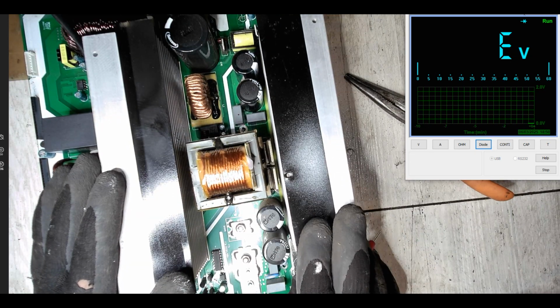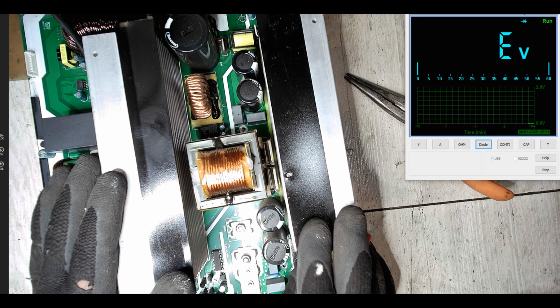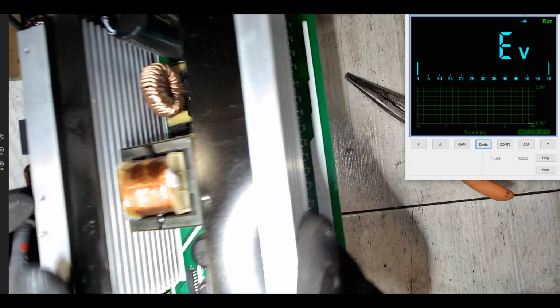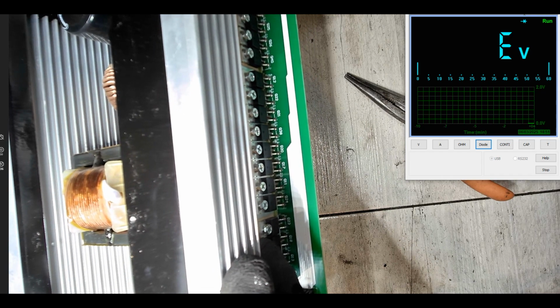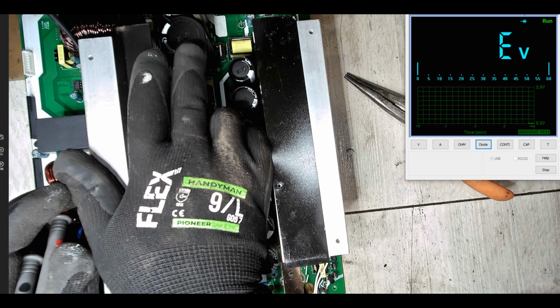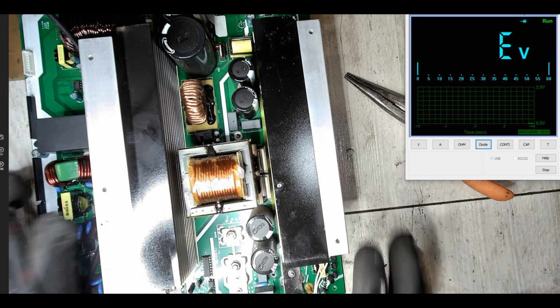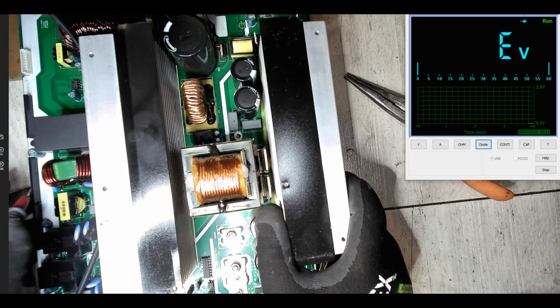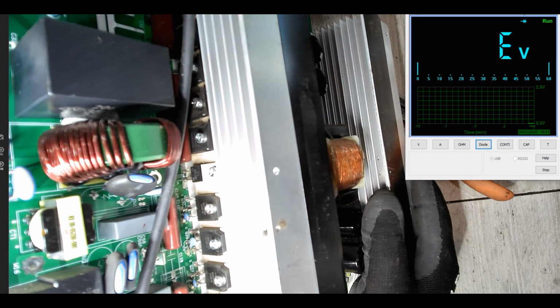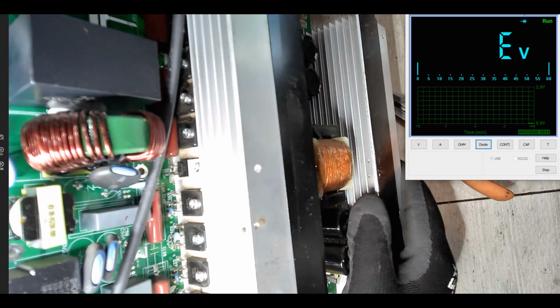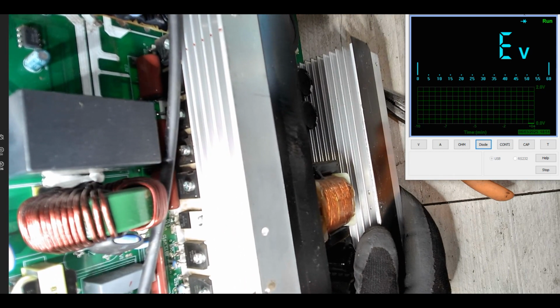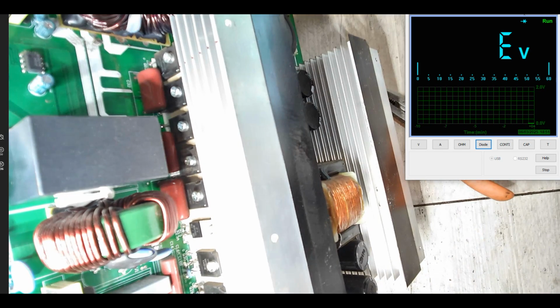See, this heatsink is for low voltage. So what's happening is all of those MOSFETs you see there, they are going to change the low voltage 48 volts to 400 volts with the help of this transformer. So on this side, we're going to have the IGBTs that change the 400 volts to AC. So these are the IGBTs that we need to check, those ones there. These are output IGBTs.